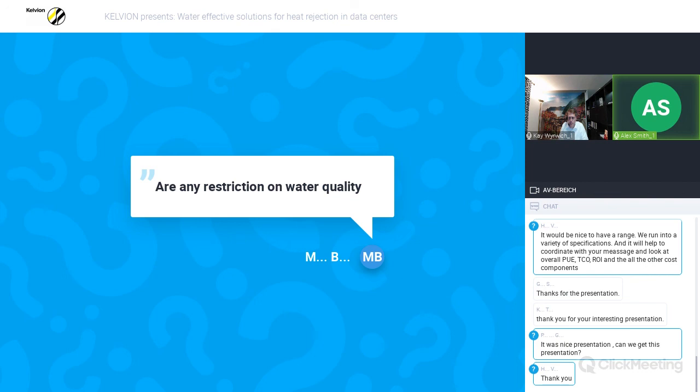It does vary from site to site. With pad systems, we tend to encourage people to get water quality reports for where they are, because then we can tailor the pad system much better. But yes, there are people looking at using gray water and wastewater, return water, rainwater. Pad systems are generally more forgiving for those kinds of things. You just have to take those things into consideration, so you may require more maintenance. There will always be a downside somewhere.